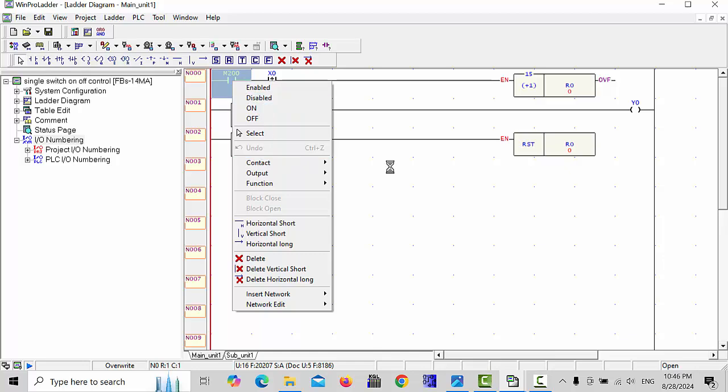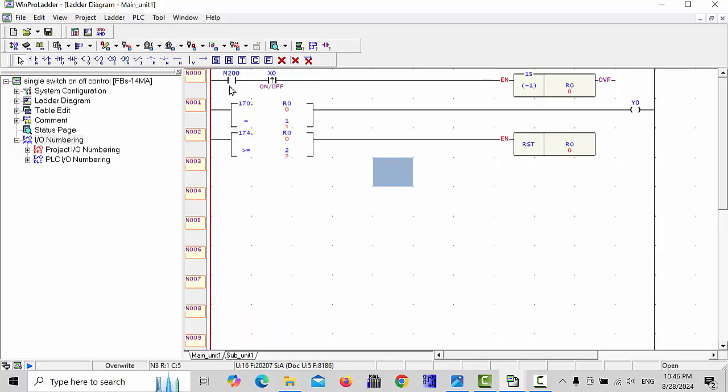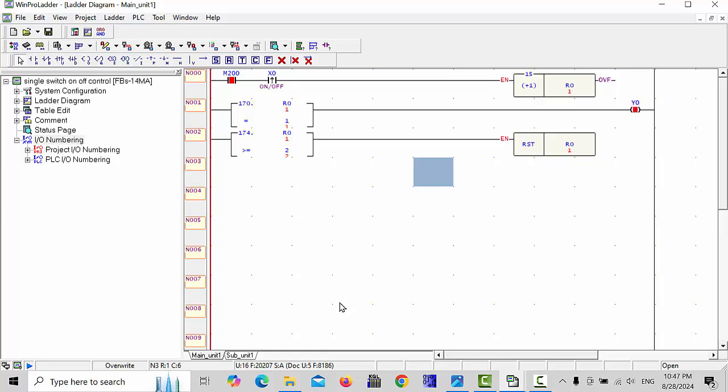Make it run condition and you can check your control. First make your emergency button on. And after, give just one signal to the X0. As you give the signal at X0, your Y0 will be on. And as you again signal give to the X0, your Y0 will be off. Again when you give signal, Y0 will be on, and again you give the signal, Y0 will be off. So this way you can use this single switch on/off control with any PLC.